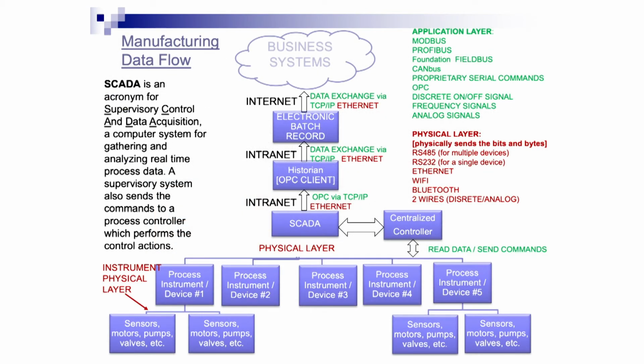So there's a lot of information on this slide, but the main thing is the sensors are down at this lower level here. The sensors could be on their own connected to a monitor. They could be on a bioreactor connected up to a process instrument. But the whole thing, particularly with continuous processing and sensors, you want all your sensors to be able to report up to a centralized controller through different application layers, which are kind of like your languages: Modbus, Profibus, all different types of application layers. So when you're looking at different technology, you should make sure to have these available features to talk upwards through some sort of physical layer to a centralized controller, because particularly with continuous processing, you want to be able to monitor the whole process.